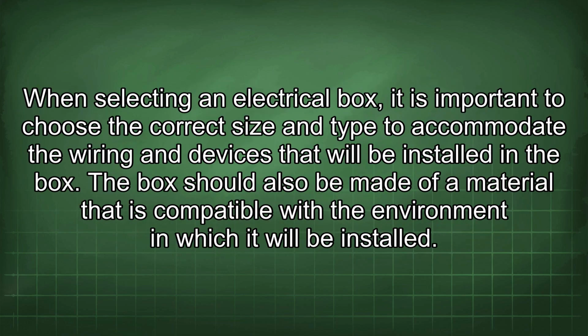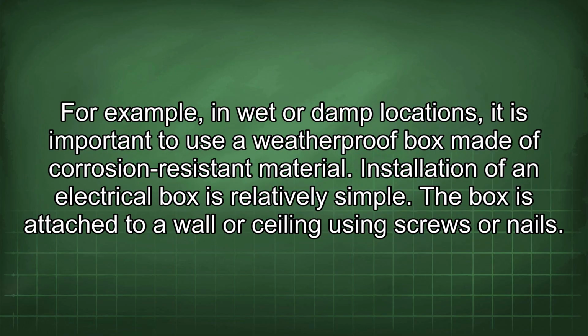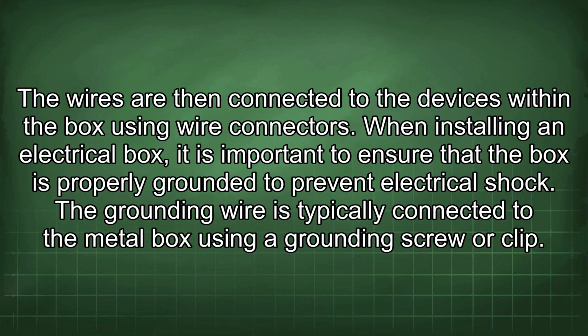When selecting an electrical box, it is important to choose the correct size and type to accommodate the wiring and devices that will be installed in the box. The box should also be made of a material that is compatible with the environment in which it will be installed. For example, in wet or damp locations, it is important to use a weatherproof box made of corrosion-resistant material. Installation of an electrical box is relatively simple. The box is attached to a wall or ceiling using screws or nails. The wires are then connected to the devices within the box using wire connectors. When installing an electrical box, it is important to ensure that the box is properly grounded to prevent electrical shock. The grounding wire is typically connected to the metal box using a grounding screw or clip.